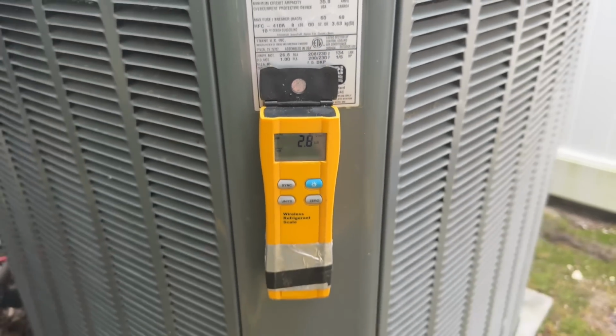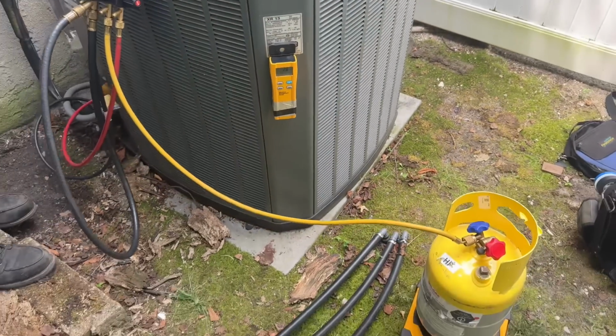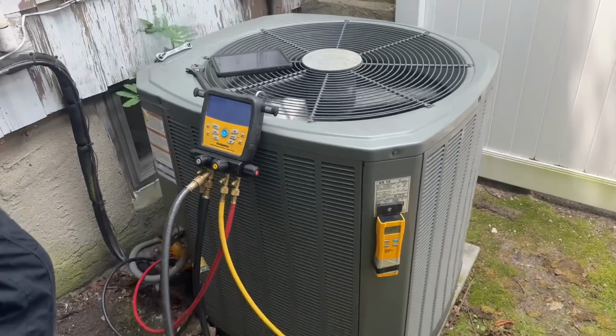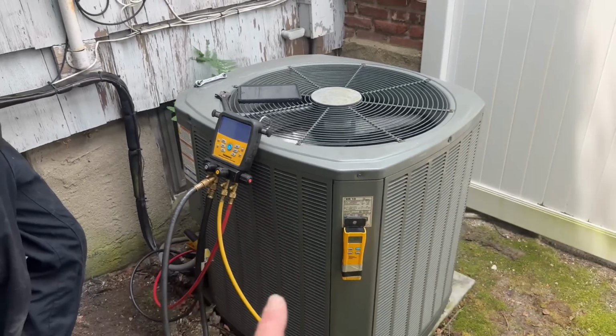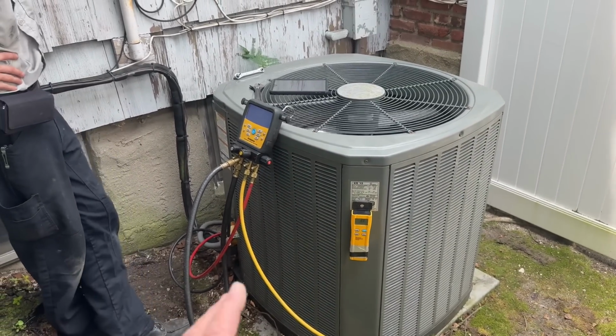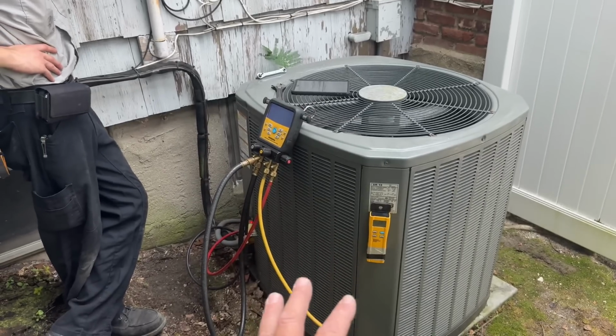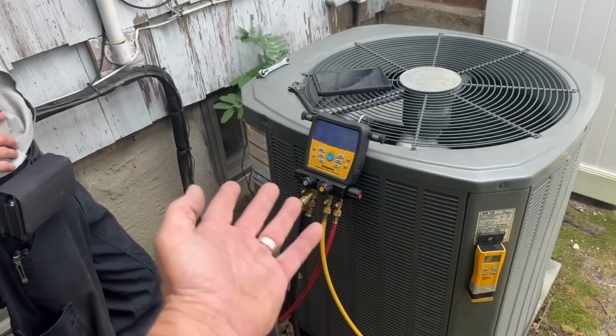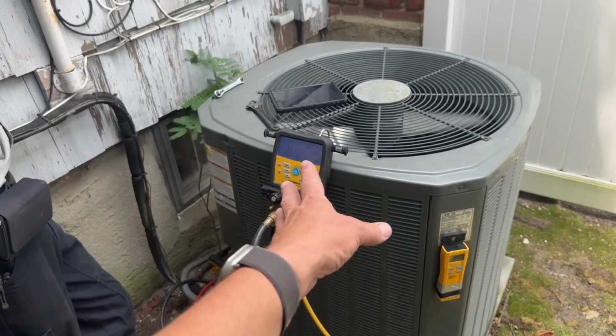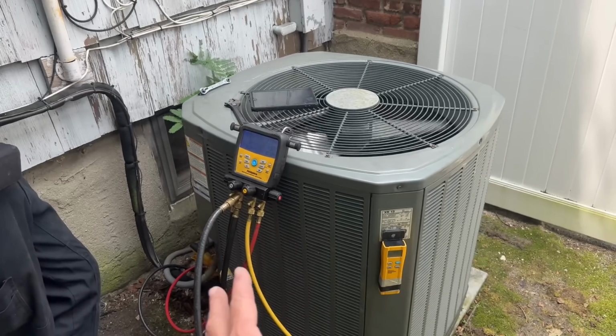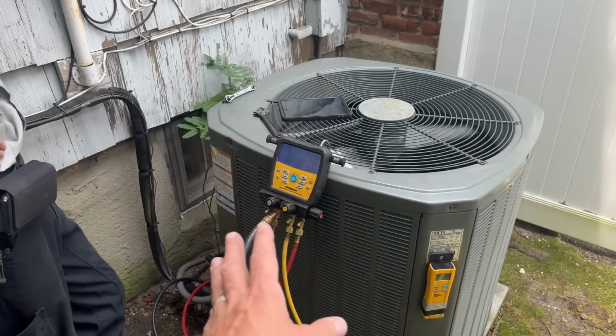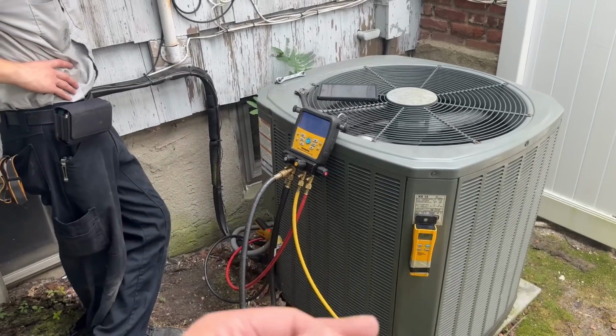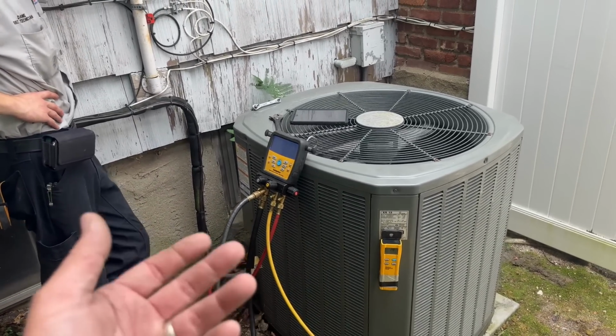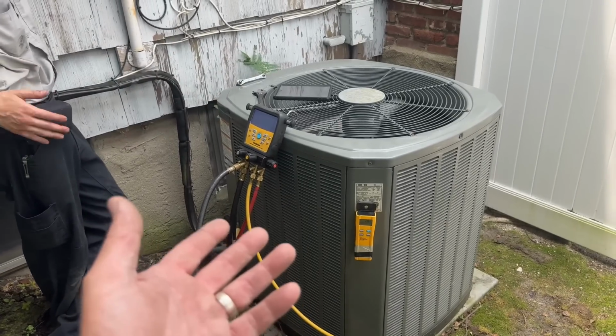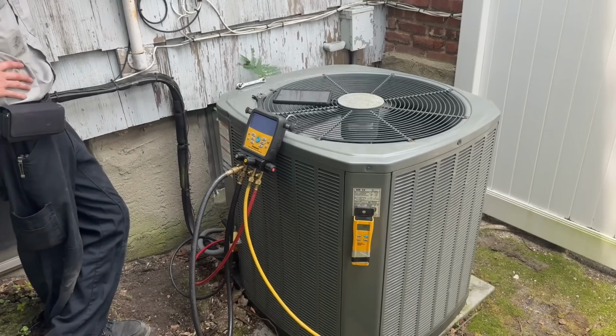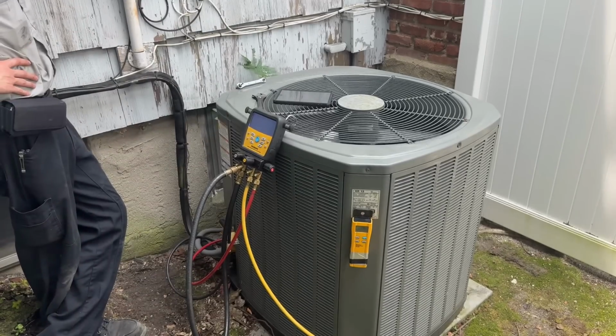All right, so we ended up actually recovering a little bit of refrigerant from a slightly overcharged system. Now, keeping it real, full disclosure, last week I was here because the system was freezing up. When I checked my refrigerant pressures, we were kind of where it is there now. We were at 109, I think it was a little over 100, and we were low 300s. I had low subcooling, and my evaporator temperature was slowly getting to 32 degrees. And when it gets to 32 degrees, the humidity being extracted from the air by means of the refrigeration cycle is going to freeze on that below-freezing coil, and then you have ice forming, icebergs and shit like that.